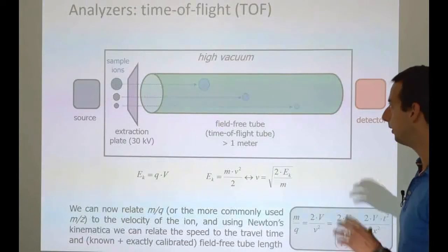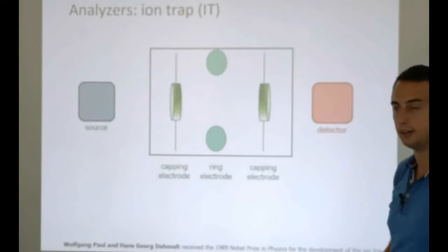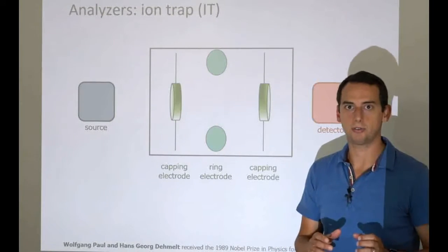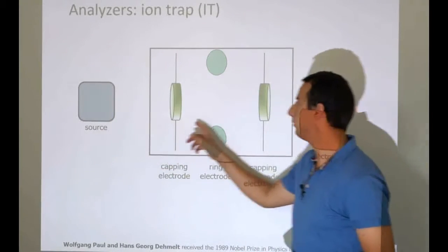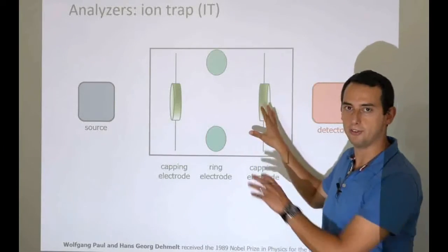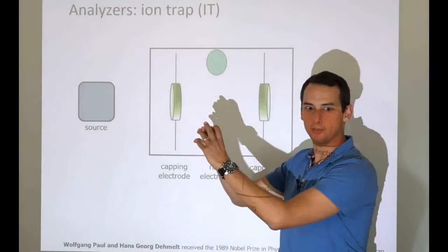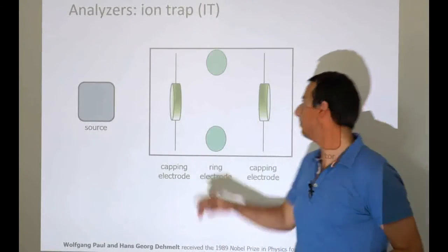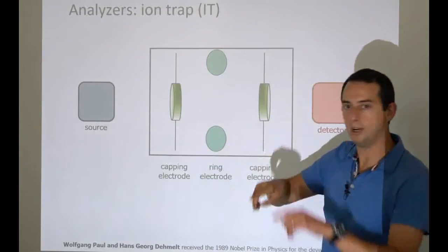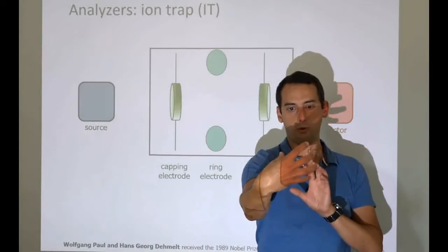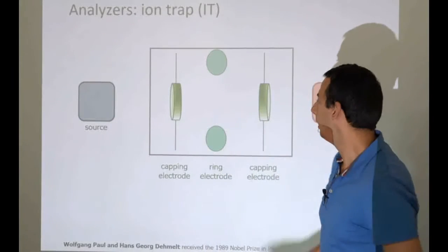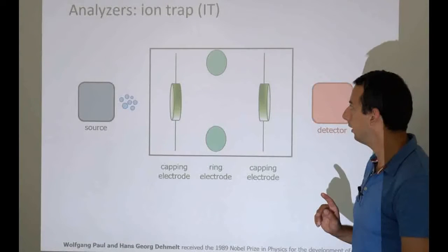Without further ado, let's go on with the next analyzer — one of my favorites: the ion trap. An ion trap analyzer does exactly that; it is a trap for ions. We have the source over here, and then there is a box: a three-dimensional structure with a round opening on one side and a round opening on the other side, essentially a tunnel through the box. In the middle of the box we have a ring — a central ring electrode. These two openings (capping electrodes) and the central ring electrode all have a current on them, and the currents are a little bit special.